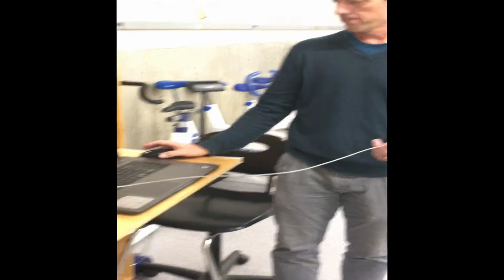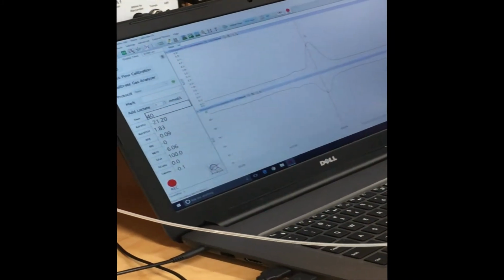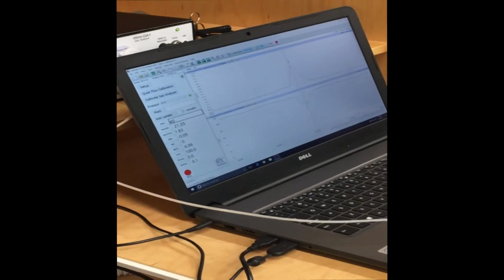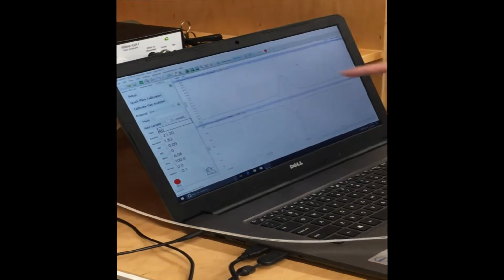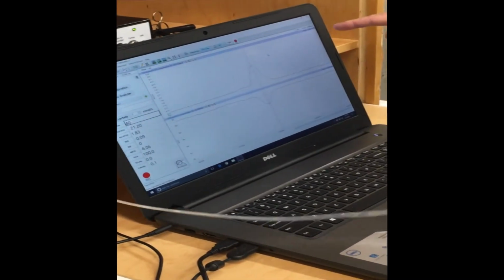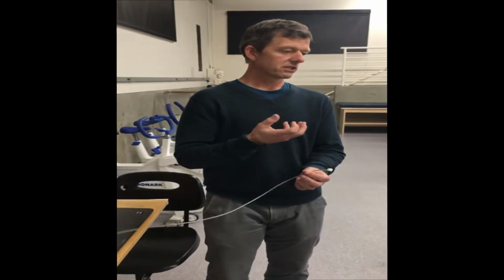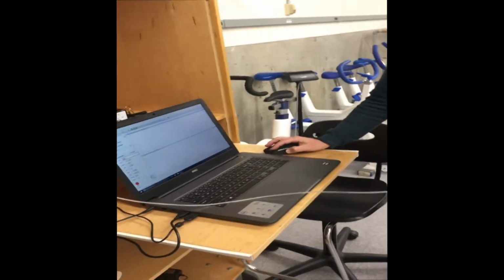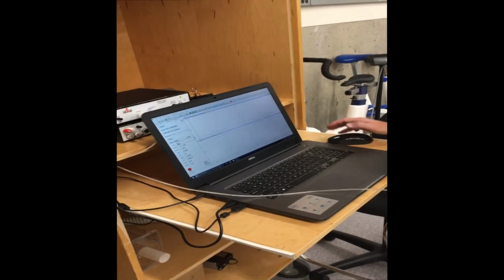So in order to get those values, we click stop. We go to the single cursor, and then we move the single cursor to the peak for the CO2 and the oxygen. So right now, that's the peak of the CO2, and it's saying the CO2 percentage was 3.09% CO2. So my maximum CO2, my end tidal CO2 was 3.09%. You may need to move this back a little bit, but our lowest oxygen concentration was 17.65%. So that is how you're going to monitor your CO2 concentration and how you're going to monitor your O2 concentration.